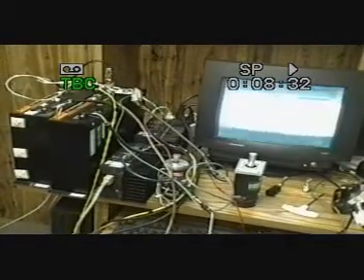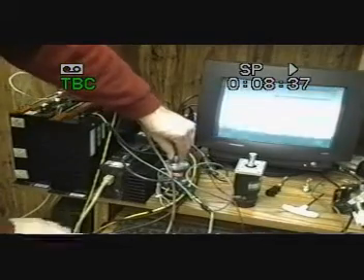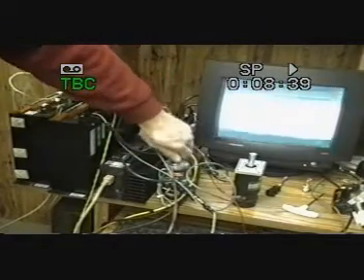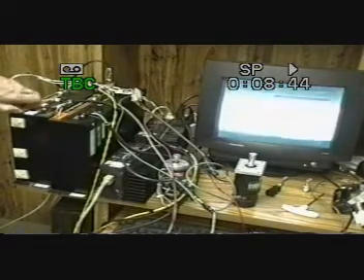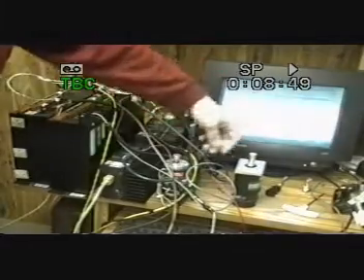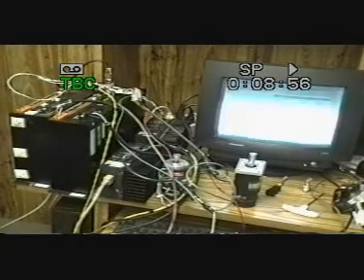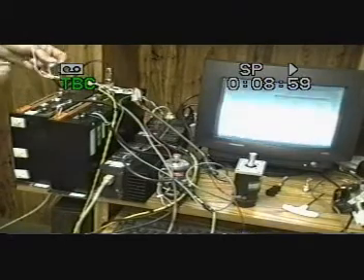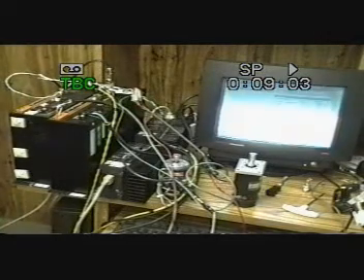I have restored the encoder wire back to the shielded one so you can see it. As I slow this one down, you'll notice that that one does not fault out. As a matter of fact, I can stop it and start it as I did before, and we will not fault out. That will continue to run for as long as we need. I'm going to conclude with the fact that I believe the problem with your press is the cable that's inputting to P4 and or the emulator.